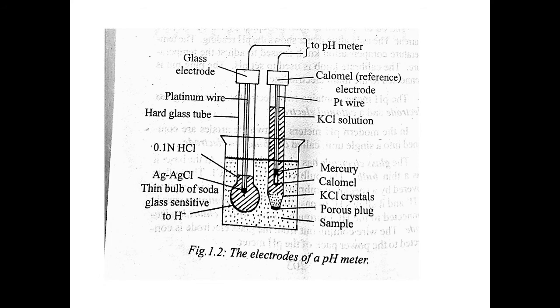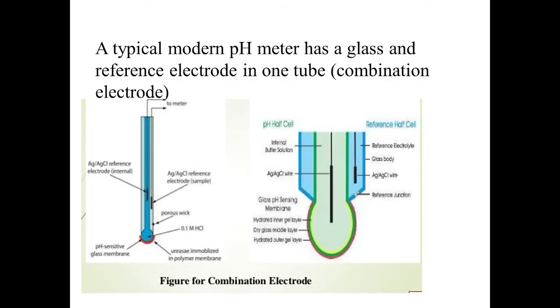The free end of the calomel electrode has a porous ring. At the bottom you can see a porous ring. The base of the electrode is deposited with KCl crystals, and the remaining portion is filled with KCl solution. So it contains potassium chloride crystals and potassium chloride solution. The glass electrode placed in the test solution constitutes one half cell, and the reference electrode is the other half cell. So the two half cells together are connected to the pH meter. Now, a typical modern pH meter does not use these two electrodes. It has a glass and reference electrode in only one tube, called a combination electrode. You can see it here.